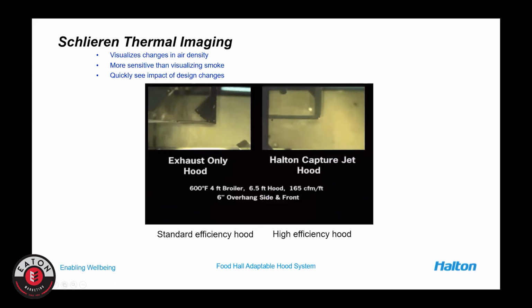So what we're seeing here, at the front of this hood, you can see convective heat spilling into that space. This is called a Schlieren thermal image. It's a photo process that allows us to visualize changes in air density. So we're looking at convective heat here. There's no cooking being done. There's no smoke being generated in this image. So once again, this is what causes the temperature in that kitchen to increase. This is carrying that submicron grease, that respirable particulate that tends to coat the ceiling tiles and the stainless surfaces.